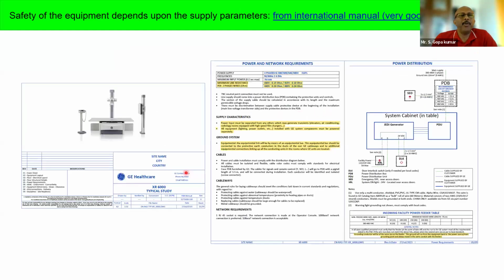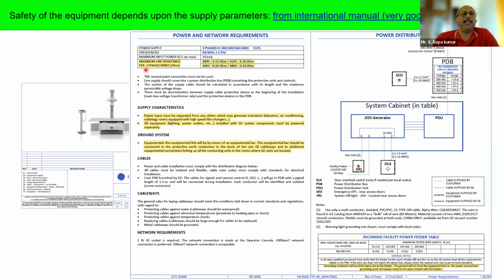Now, for example, I'm showing you the catalog of a biomedical equipment made by GE. This catalog is taken from the international manual of the manufacturer. I would say it's written extremely well. You can see here some of the parameters. Maximum line resistance means the impedance of the incoming lines should be within this particular limit to ensure automatic disconnection or to ensure safe operation of the particular device. A power input must be separated from any other which may generate transients. For all equipment installed, it also talks about the equipotential bonding, how to make equipotential bonding.